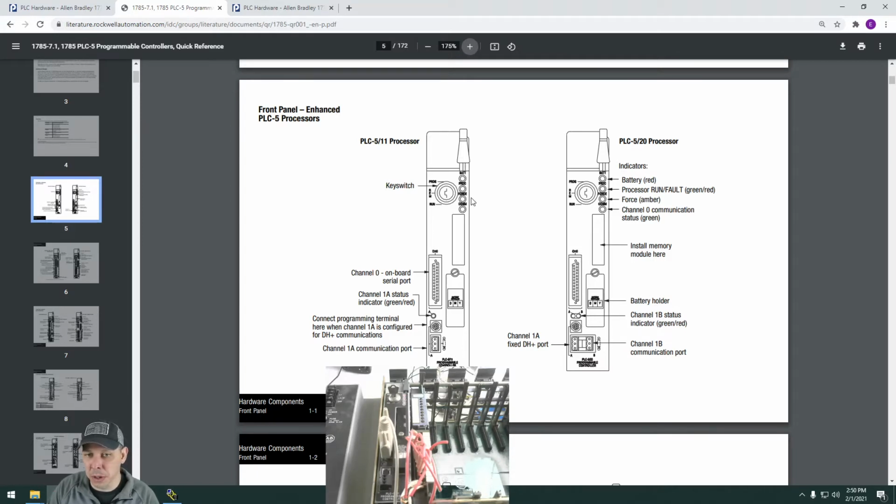If you have a force installed, you could potentially have safety options overridden, so it could be a dangerous situation. So that's just letting you know, if you look at the rack, that there is a force installed, so be extra careful, or we go online with the logic and see what that force is.